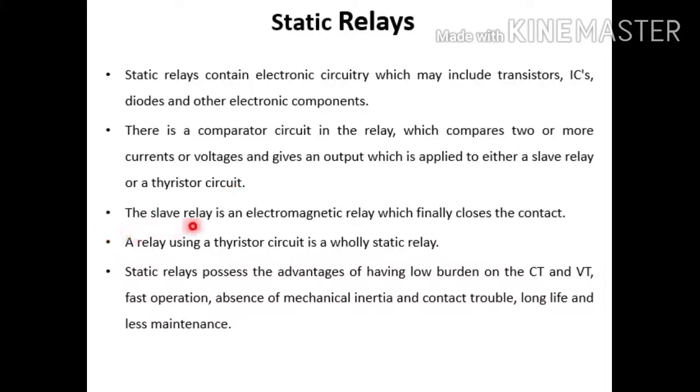The slave relay is an electromagnetic relay which finally closes the contacts. A relay using thyristor circuit is called as static relay. Static relays possess the advantage of having low burden on the current transformer and the voltage transformer, fast operation, absence of mechanical inertia and contact trouble, long life, and less maintenance.